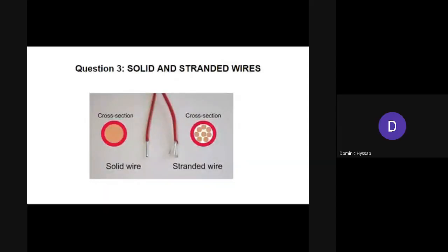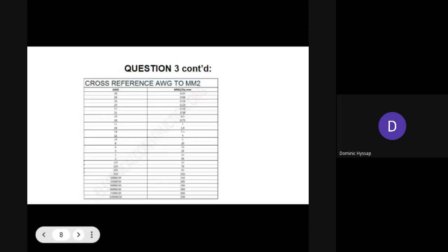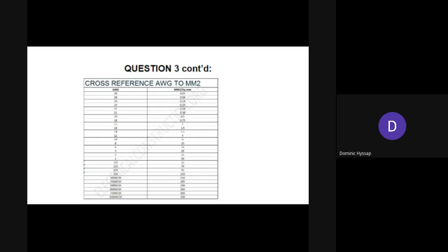If you use a long, thin wire, the performance of the compressor will be affected due to increased resistance causing a voltage drop, which in turn affects the oxygen purity of your concentrator. There are two types of cables: solid wire and stranded wire. Stranded wires are mostly used in concentrators because they are more flexible. For stranded cable, calculate the cross-section area of a single strand and multiply by the total number of strands, then refer to the AWG chart in the graphics to identify the correct wire gauge number.